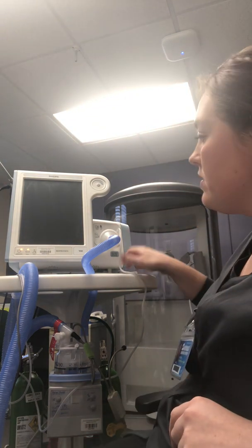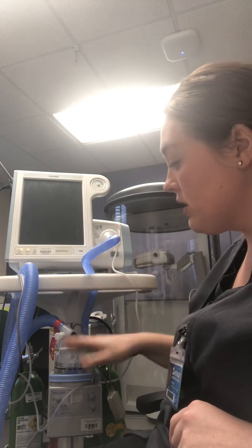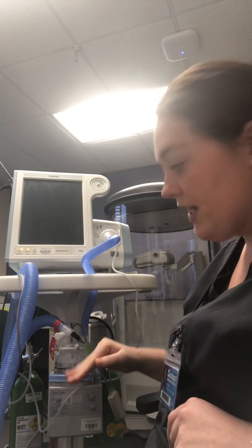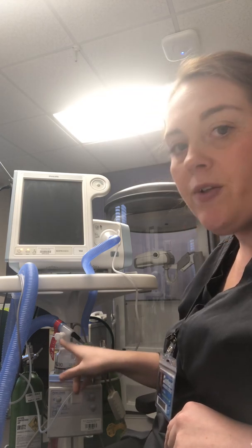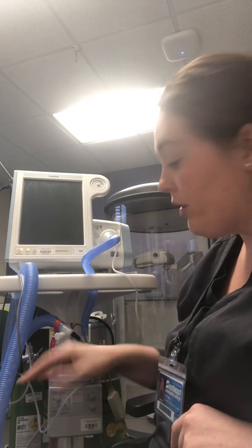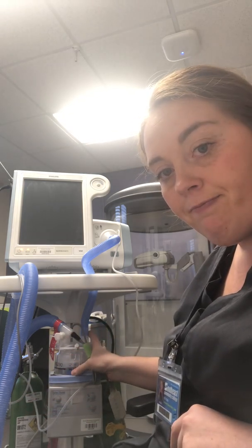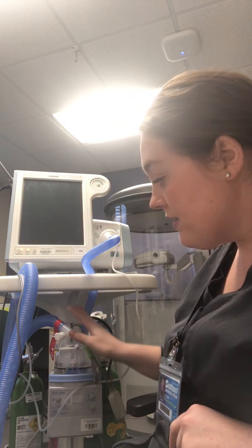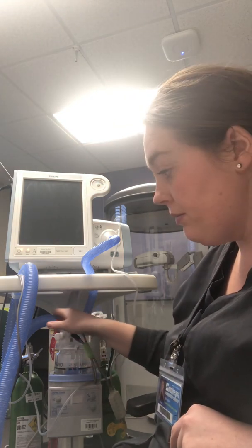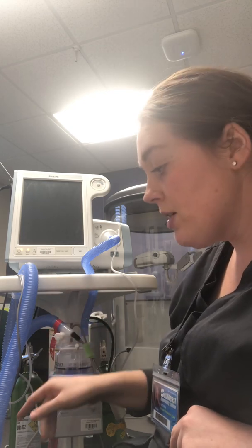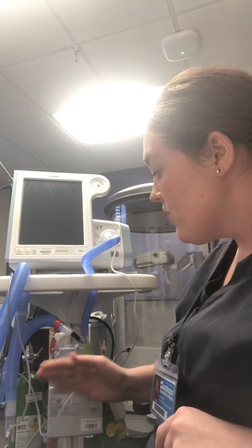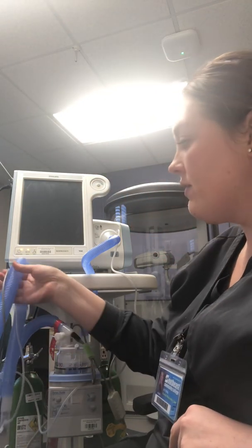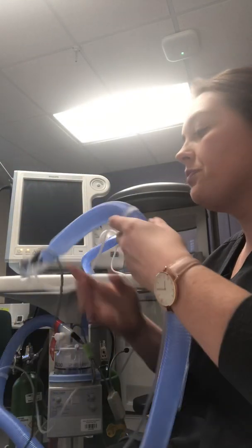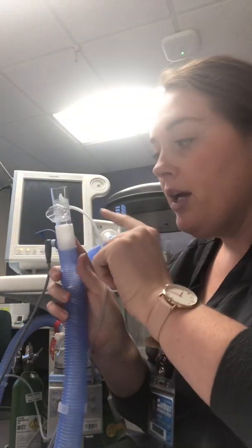So this is the pressure, and then this is what's going to go to the heated humidity to get that to the patient. There's a little spike right here that we use to spike sterile water for oral inhalation. That water will fill this little chamber, and then it's attached to another part of this blue corrugated tubing, which does have heated coils in it. You can sort of see maybe. So we have a temperature probe here on this end, and then we're going to also have a temperature probe here on the patient side as well. So here's our temperature probe.